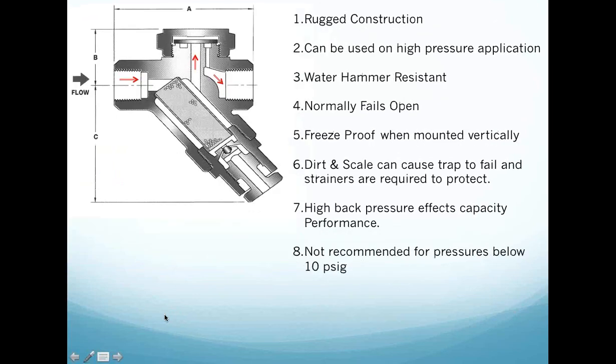The next trap that we're going to look at is a thermodynamic disc trap. This is a very common trap inside of industry for drip main applications. The way this trap works is really simple: as condensate is formed, we hold the steam inside of the steam space, and we're using the latent heat of vaporization out of the steam.